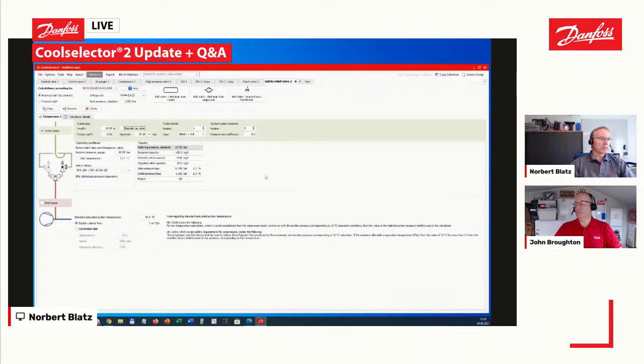You can see here, now you get an okay result. And by that you're on the safe side and you don't run into a problem that the outlet tube will be sticking with frozen CO2.